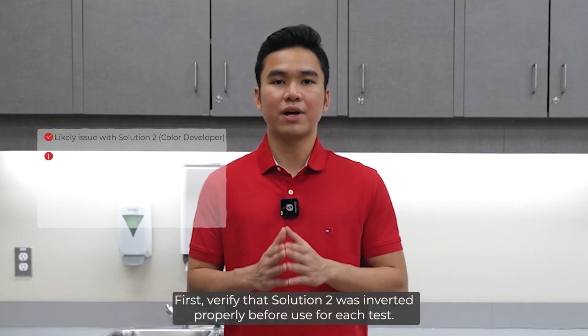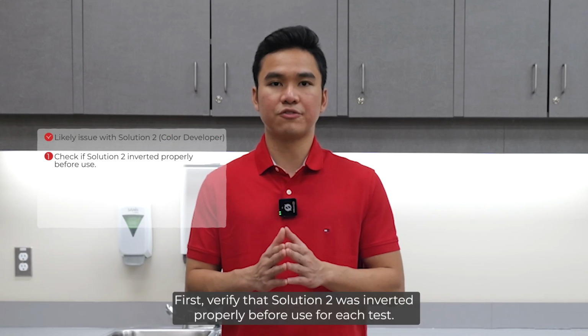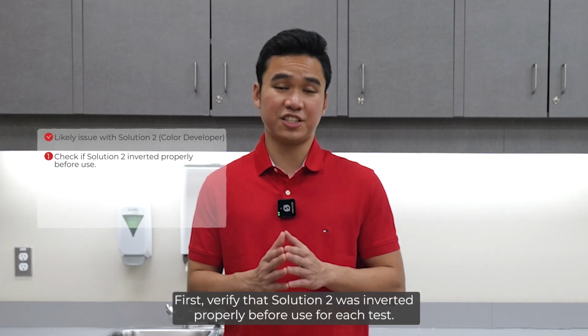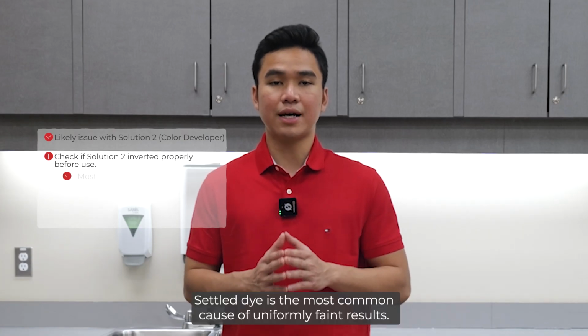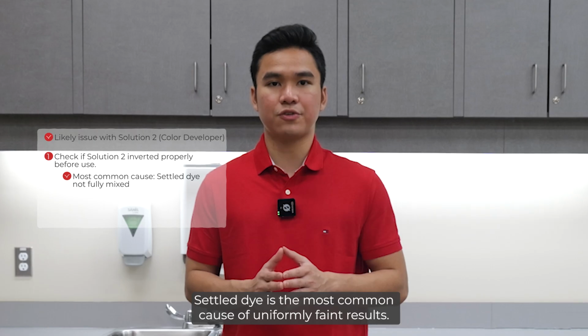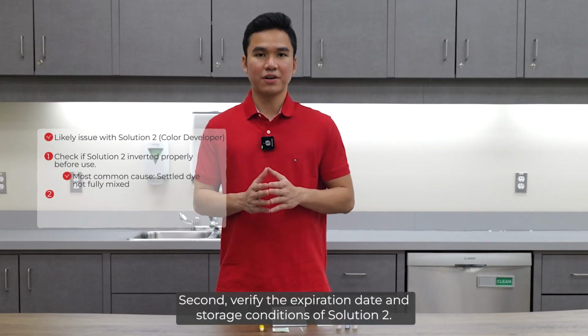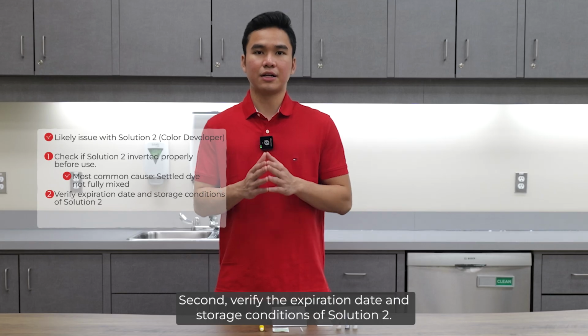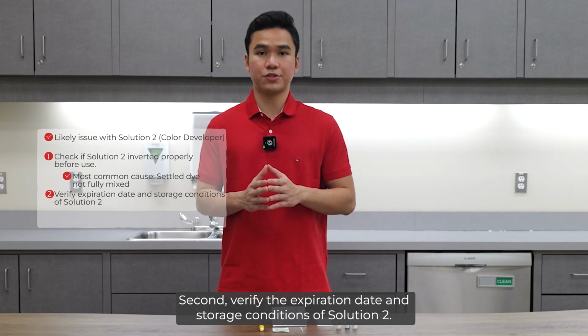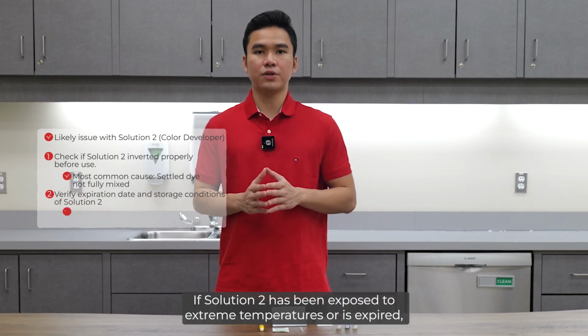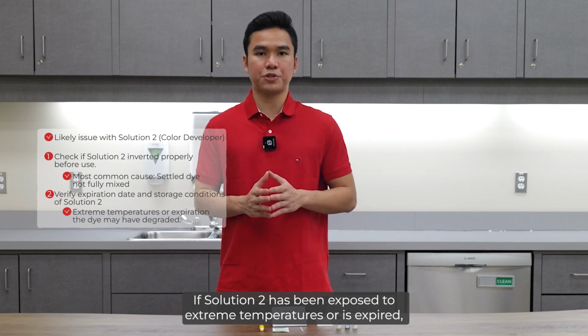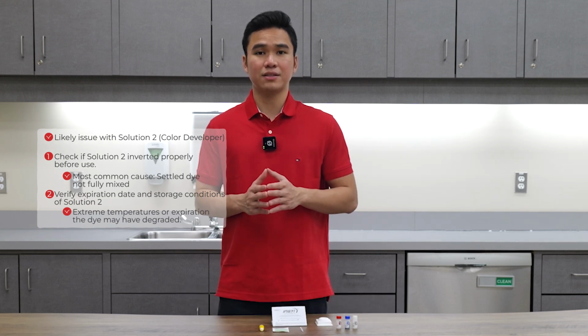First, verify that solution 2 was inverted properly before use for each test. Settled dye is the most common cause for uniformly faint results. Second, verify the expiration date and storage conditions of solution 2. If solution 2 has been exposed to extreme temperatures or is expired, the dye may have degraded.